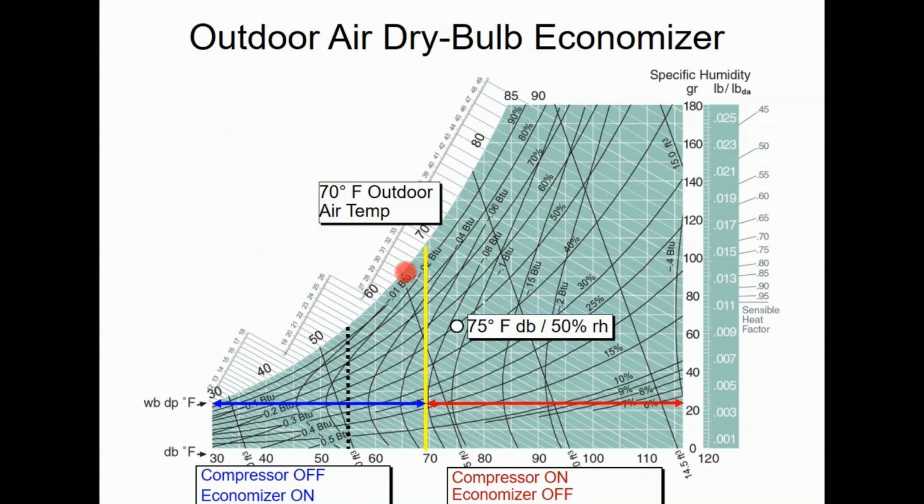I've almost doubled the amount of moisture if I'm right here on the cusp as opposed to over here on the cusp, right? So this area right here, you probably heard me refer to it as the triangle of death. I want to avoid this area. It's too humid for me to deal with on my building, and it will increase my callbacks and problems.